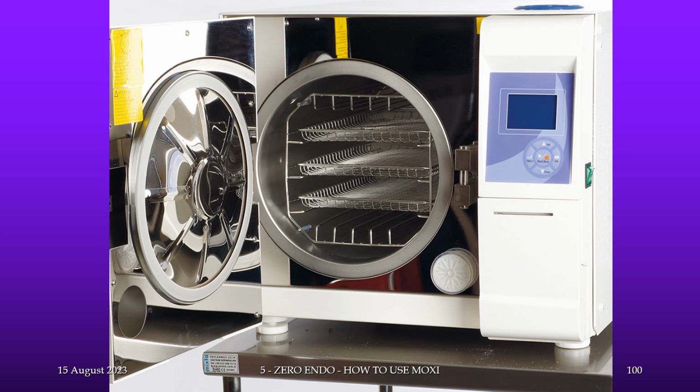But in case of super fast flash autoclaves taking only a few minutes, there is not enough time for the bottle's internal water to become steam of equal pressure and temperature. These are only for surface sterilization, especially for metallic instruments, and not for bottles or vials.